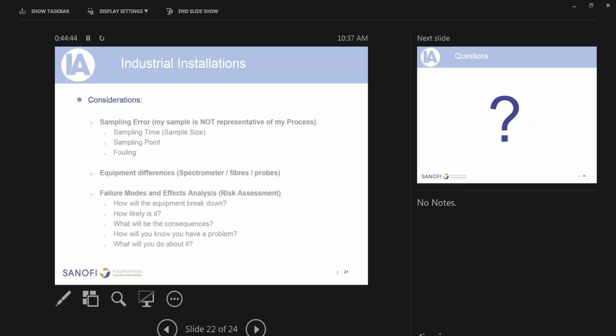Finally, if we're putting a spectrometer into a production plant, we generally perform a risk assessment called an FMEA, which is a failure modes and effects analysis. So we think about how this equipment will break down once it's in a production plant, how likely that is to happen, and then what would happen if the equipment were to stop working. What would be the consequences for the batch? How would you even know that your equipment had broken down? How soon before you reacted to it? And then finally, once you knew that something had happened, what would you do about it?